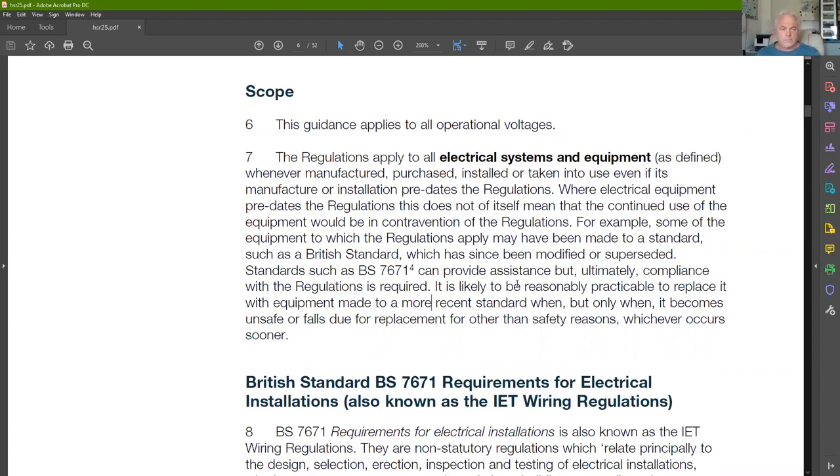It's likely to be reasonably practicable to replace equipment with equipment made to a more recent standard when it becomes unsafe due to damage, or when it falls due for replacement for other than safety reasons — whichever occurs sooner. So you don't have to immediately replace pre-1989 equipment to apply these regulations, but when selecting new equipment you should ensure it complies with more modern standards.